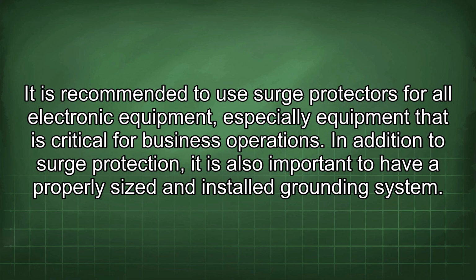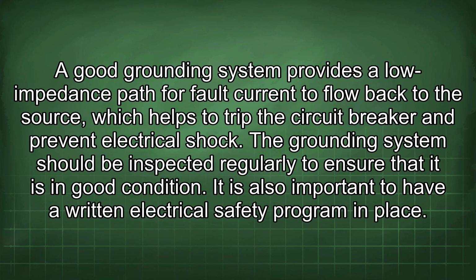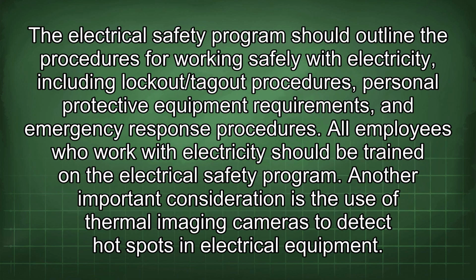In addition to surge protection, it is also important to have a properly sized and installed grounding system. A good grounding system provides a low impedance path for fault current to flow back to the source, which helps to trip the circuit breaker and prevent electrical shock. The grounding system should be inspected regularly to ensure that it is in good condition. It is also important to have a written electrical safety program in place. The electrical safety program should outline the procedures for working safely with electricity, including lockout/tagout procedures, personal protective equipment requirements, and emergency response procedures. All employees who work with electricity should be trained in the electrical safety program.